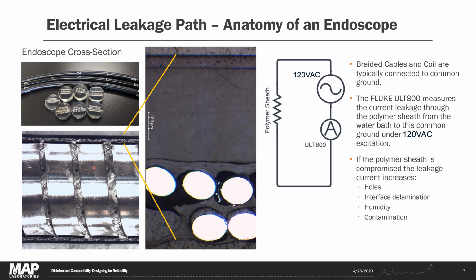Here I've cross-sectioned an endoscope to give us an idea of the construction and the electrical leakage pathway. Endoscopes are typically constructed of this inner metal coil and a wire braid. These are both typically connected to a common terminal. The ULT 800 applies 60 volts AC between that common terminal and the probe that was in that water bath. So you have 60 volts across this material here.